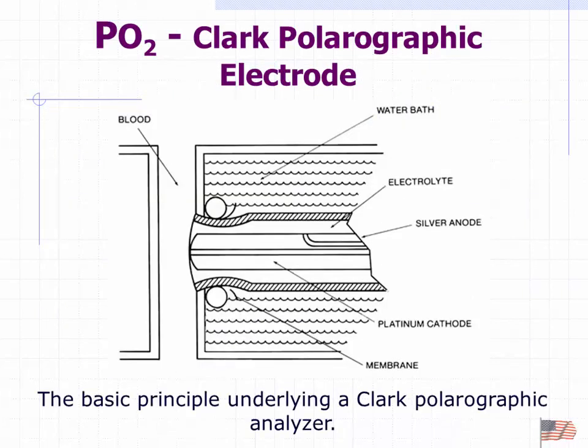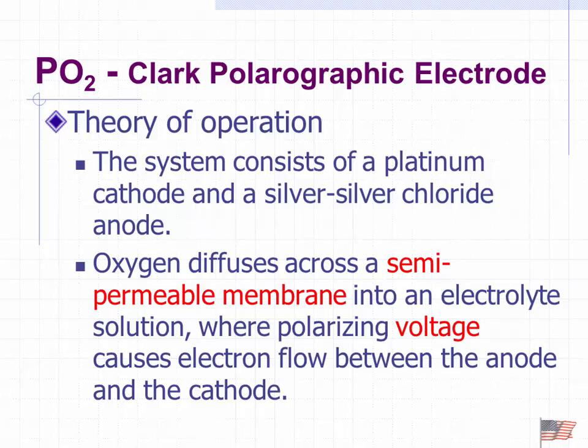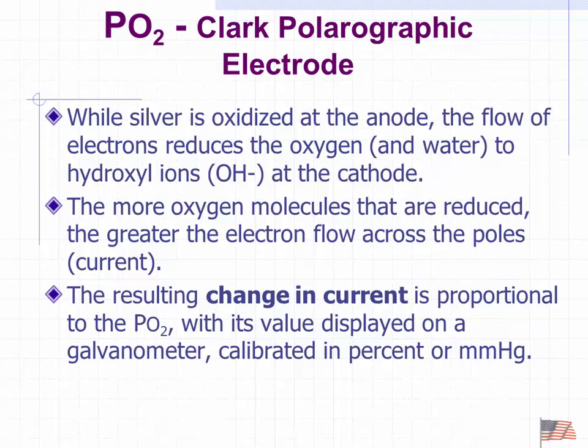We'll talk about temperature change in a second. Let me skip that slide. The last one is a Clark electrode, a polarographic electrode, which basically is measuring the amount of current that is created as you have an oxidation reduction reaction. Oh my God, there's that stupid word again. All you need to remember is that it's got a platinum cathode and a silver chloride anode, but again, what we're seeing here is the reduction of oxygen, and that in the process generates a current. And as the current is generated, I can measure how much current is generated, and it's proportional to the partial pressure of the oxygen. So the more current, the more PO2 that is present. I don't really care that you know that silver is oxidized at the anode, and there's a flow of electrons to the platinum cathode, blah. Just know it's an oxidation reduction reaction that generates a current.